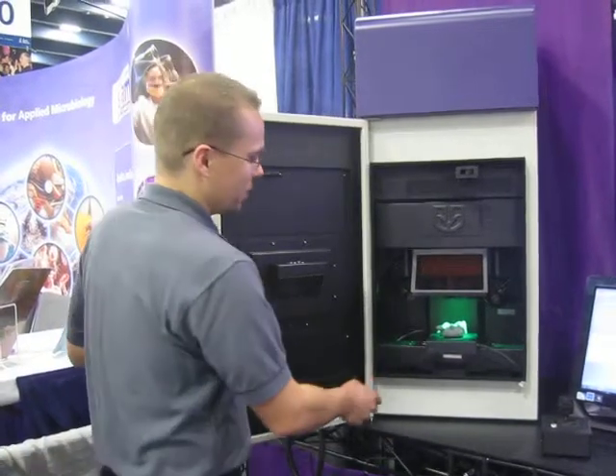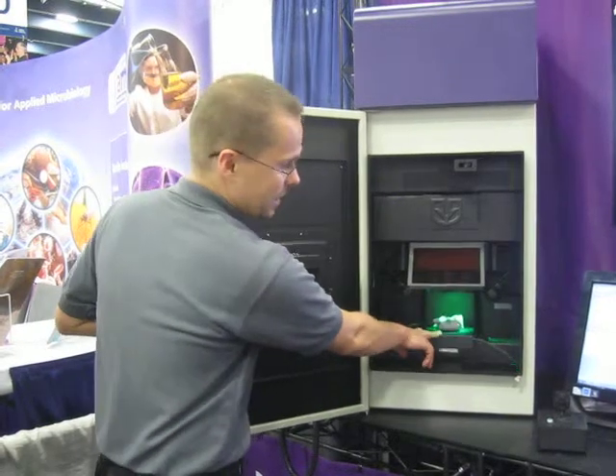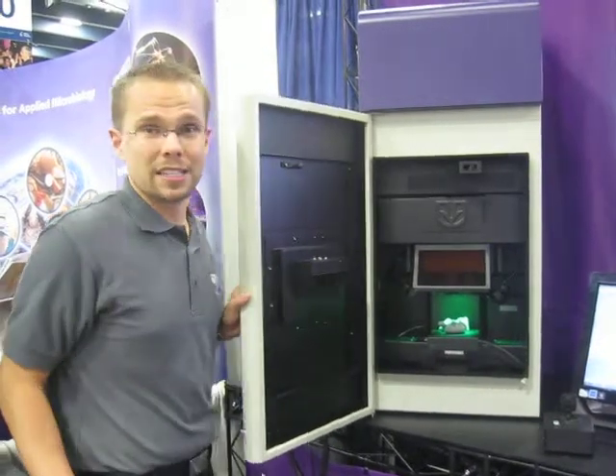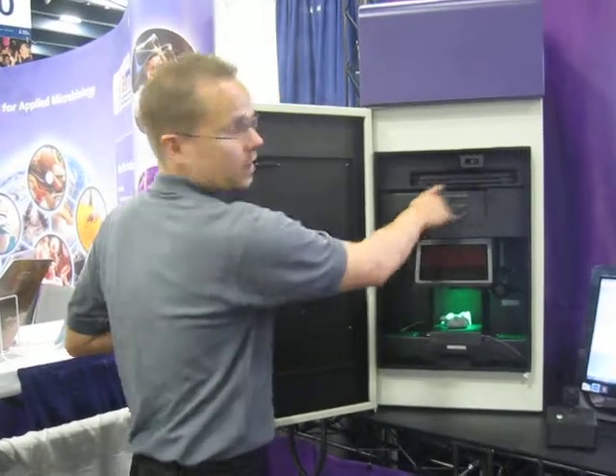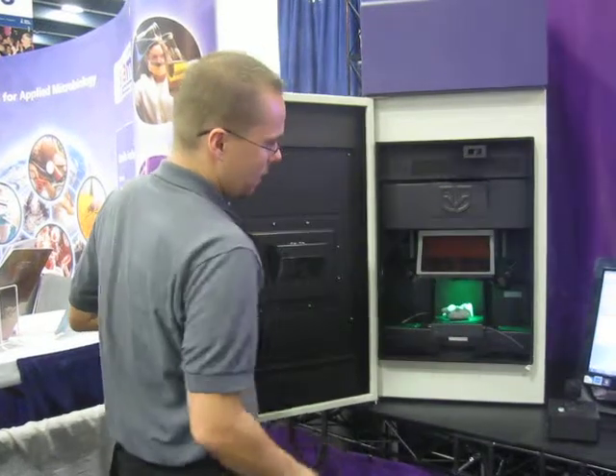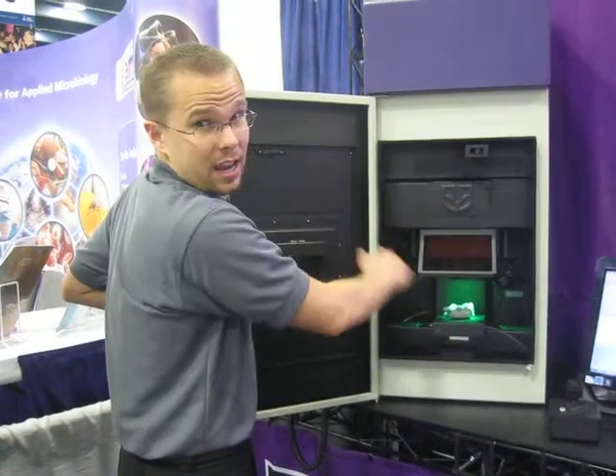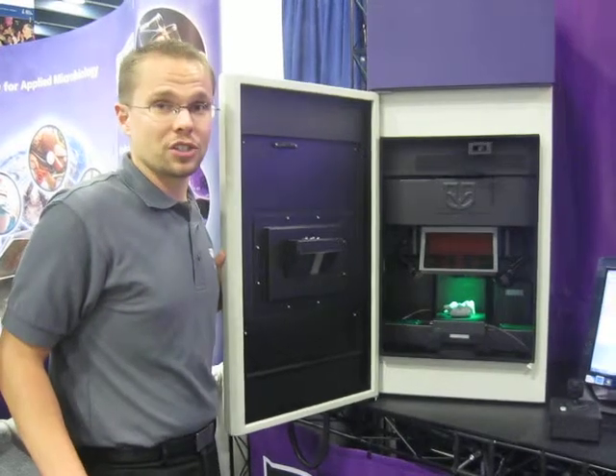Inside the darkroom here you'll see that we have a warming plate that rolls out. This is integrated into the system so that the animal can be placed directly on the platform. The system also integrates a four-position emission filter tray at the top, as well as lighting on the side and coaxially straight down onto the animal for higher magnification applications.